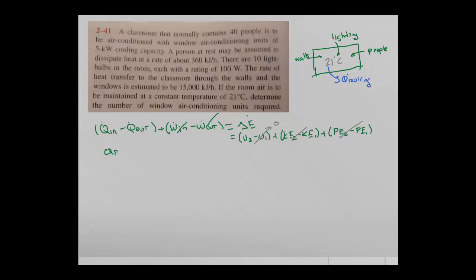We can see that Q_in should be equal to Q_out. All of the heat that we gain in the room will be removed by the air conditioning units. The Q_in will be the summation of all heat loads: Q from people, plus Q from lighting, plus Q through the walls. Starting with people, we know that we have 40 people, and each person is assumed to dissipate 360 kJ per hour.